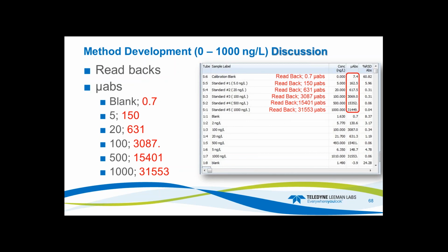If you look at the readbacks, for example, the 1,000 nanograms per liter at 31,449, my readback came back at 31,553. Those are almost bang on. And if you look at all of these throughout from top to bottom, they're almost identical to when they were with calibration. So my problem is definitely within the calibration.